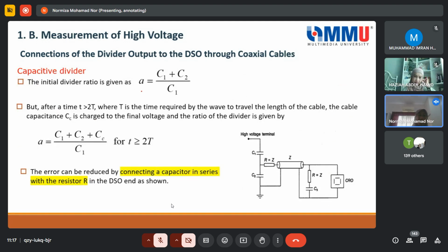So here is the effect of the cable. As you can see here, the ratio we normally obtain is like this, but because of the presence of the cable, this CC will be reduced. The error also becomes a concern to the manufacturer of the high voltage divider, so normally a capacitor in series with a resistor can be considered. That's why we normally have different cables at both ends or terminals, supplied by the manufacturer, because they have this condition already.